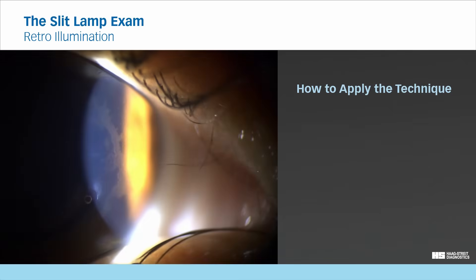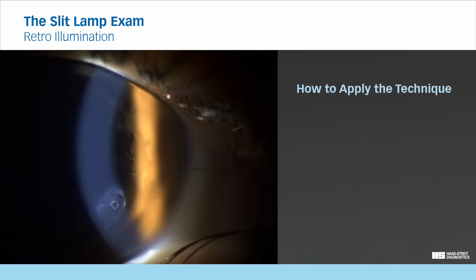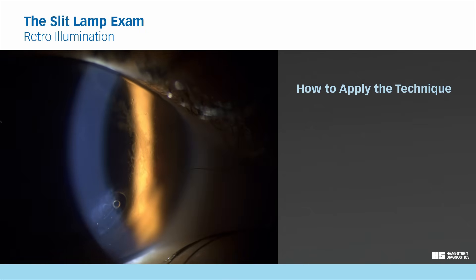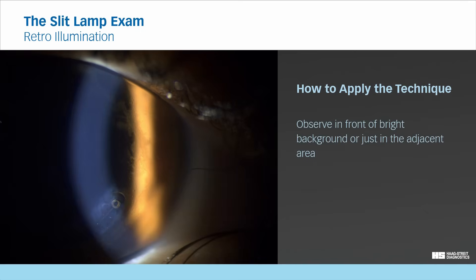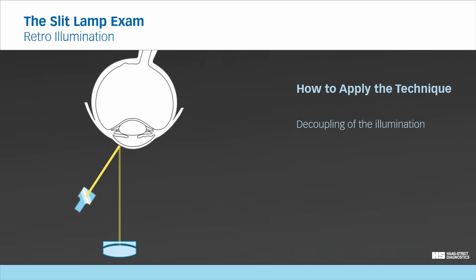To use retroillumination, focus on the area of interest and illuminate the structure behind it. With direct retroillumination, you observe directly in front of the illuminated background. With indirect retroillumination, you look just adjacent to the reflecting area. Depending on the properties of the irregularity, visibility may be enhanced by using either direct or indirect retroillumination. Due to the common pivot of illumination and microscope, the directly illuminated tissue will be in the center of your field of view, while the retroilluminated area is offset.